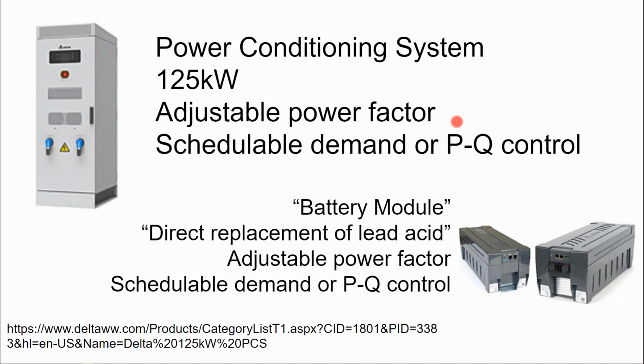For instance, if you are halfway through the month and you've never gotten anywhere close to fully draining your battery on a demand management setting, then you would want the battery to take the highest demand for the entire month already achieved and load level at that lower threshold. And again, that could also be predictable on weather. It's like, okay, well, if it's not going to be the hottest day of the month and we've already had hotter days, then maybe not run the battery so hard.